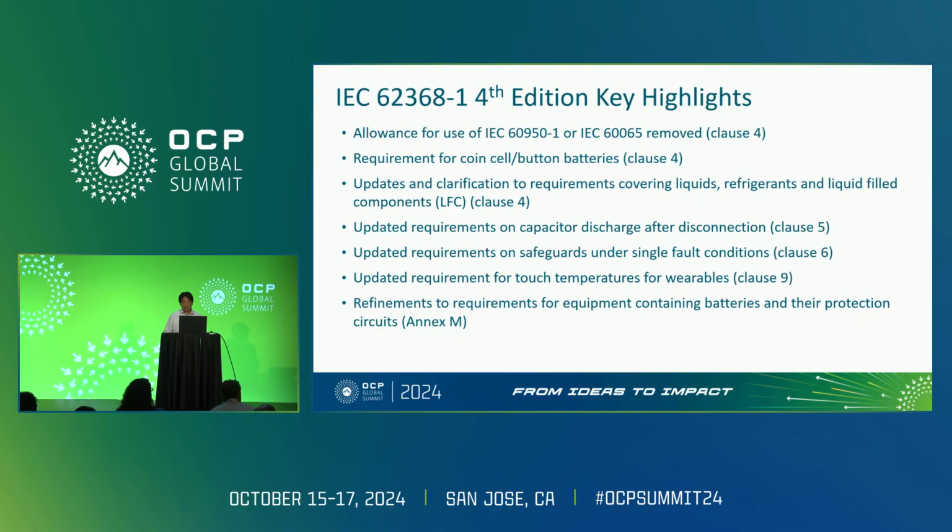And this would be much more relevant to OCP: there are a lot of updates and clarification based on the use of liquids, the liquid cooling. In the standard they call it LFC, liquid filled components. So if you have devices that are using liquid cooling, this is an area that you really want to hone in on and review, because between the 3rd edition and 4th edition, there have been a lot of updates on that. And a lot of it's really beneficial because it's clarifying a lot of things that were a little bit vague previously. So that's good.